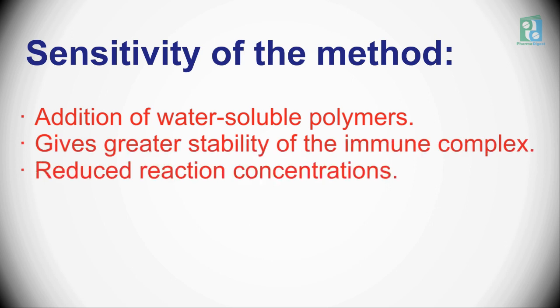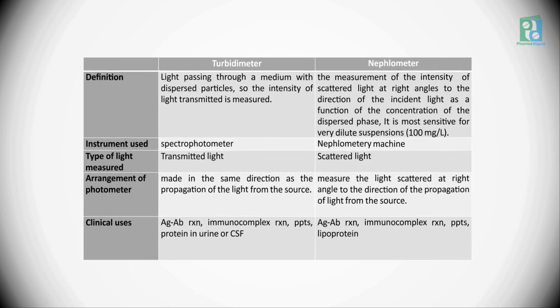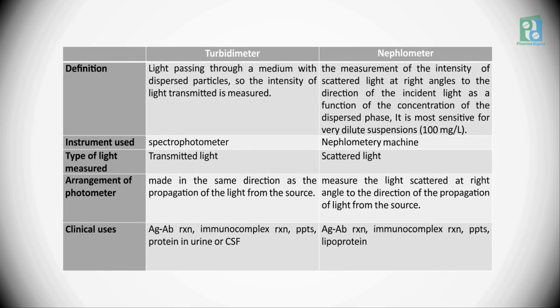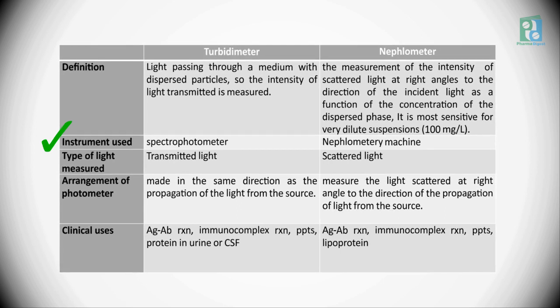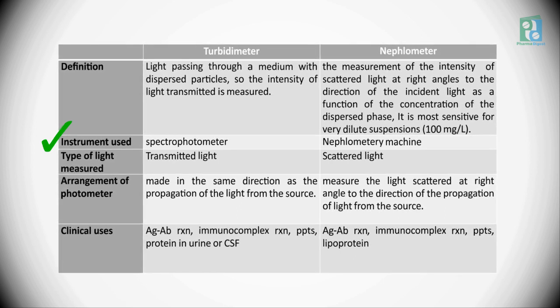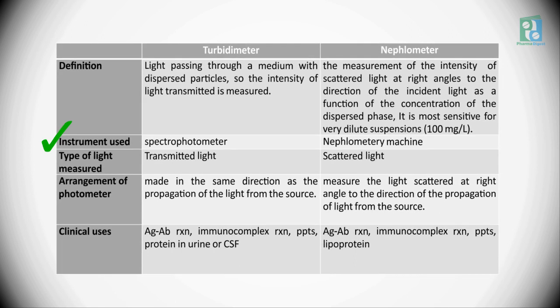Sensitivity of the method is improved by the following: addition of water-soluble polymers, which gives greater stability of the immune complex, reduces reaction concentrations, and increases sensitivity. The major difference between turbidimeter and nephelometer is the instrument used. In a turbidimeter, a plain spectrophotometer can be used. In a nephelometer, nephelometry machines are used.